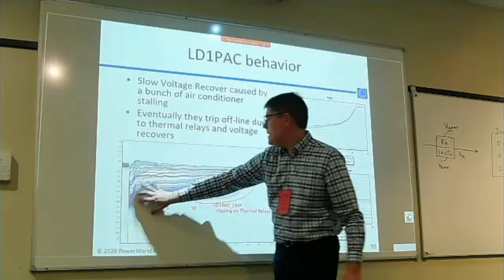This is a plot of every load bus voltage in SRP, Tucson, Southern California Edison, and APS. You can see the voltages are around 0.6 to 0.8, just kind of hanging out, and they just sit there until about 15 seconds. And then the thermal relays finally start tripping them.